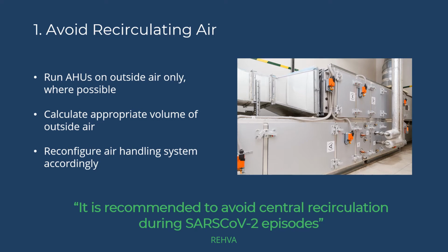The Chartered Institution of Building Services Engineers, CIBSE, recommends that any ventilation or air conditioning system that normally runs with a recirculation mode should now be set up to run on full outside air where this is possible. This advice is echoed by other industry bodies. Using fresh air rather than recirculated air will help prevent any pockets of stagnant air. Preventing recirculation and transfer of air from one room or production area to another is recommended unless recirculation is the only way of providing adequate ventilation to all occupied areas. In order to run on full outside air effectively, according to CIBSE, you need to calculate the appropriate volume of outside air required and reconfigure your air handling system accordingly to provide it.